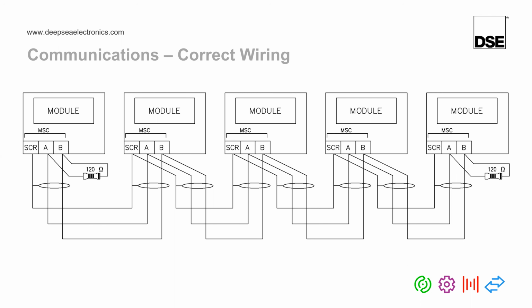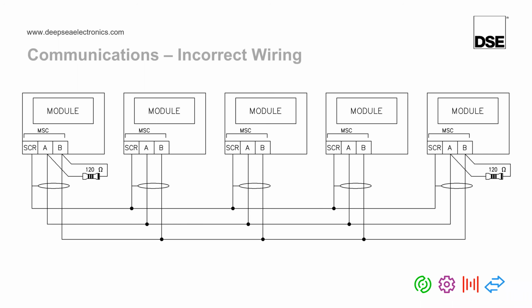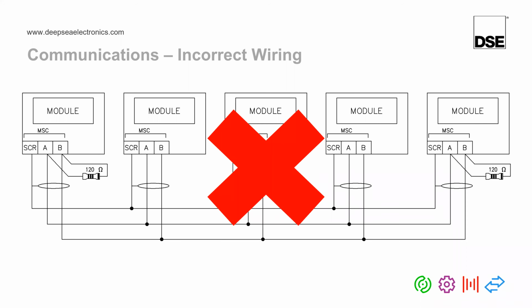If you forget to put the termination resistors in, this can lead to MSC failures. If you use the wrong type of cable, this can lead to MSC failures. And if you do not wire in a daisy chain connection, but instead this type of connection, this will also lead to MSC failures. The difference between this type of wiring and the previous wiring is that it's not daisy chained. We only have one set of cables in the terminals. This will lead to MSC failures, so we advise strongly against what we call spur type wiring, which is what is shown on the board now.